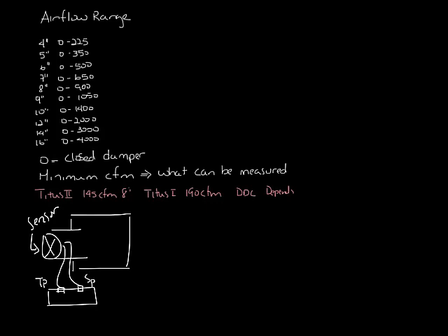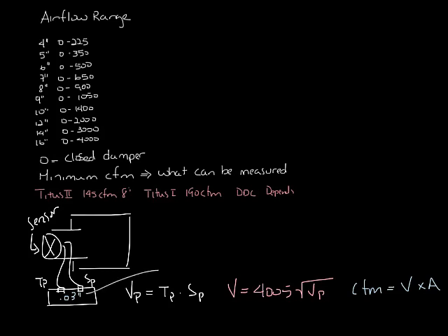If you recall, the difference between total pressure and static pressure is the velocity pressure. So the controller uses the velocity pressure to calculate the velocity of the air moving through the box. This is velocity equals 4005 times the square root of the velocity pressure, and then it can use that to calculate the CFM, which is velocity times area. So a good rule of thumb is that the pressure transducer in a controller needs about 0.03 inches of pressure differential. So using 0.03 as a guideline, you can calculate for each inlet size an approximate minimum CFM.